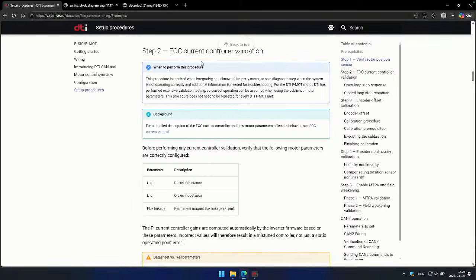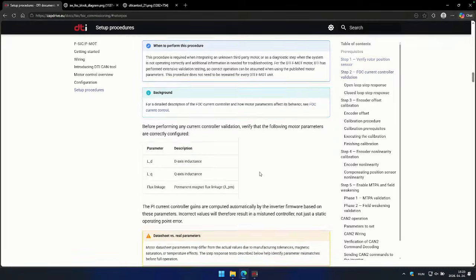This procedure has to be executed when you are working with an unknown motor with unverified parameters. The DTI motor is tested in our dyno, which means that these motor parameters are validated. So in the normal procedure, you do not need to repeat this section for every DTI motor unit. I'm showing you this section to understand and learn how to find or verify the current controller, or find issues, troubleshooting when you observe some problem.